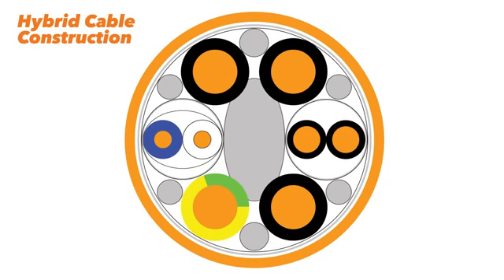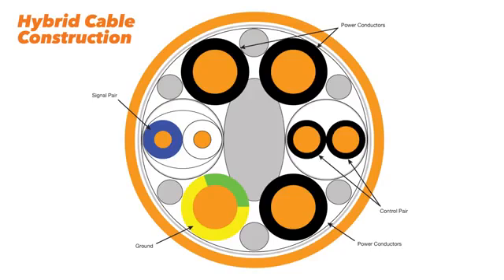The cable construction looks pretty much like a traditional servo cable. You have the four power conductors, three plus one protective ground. You have one optional control pair for the electric brake, and now the difference is you don't have a second control pair for temperature control.